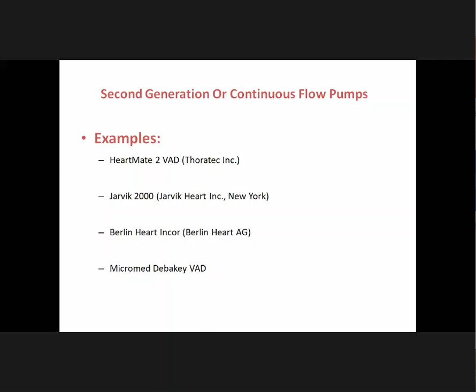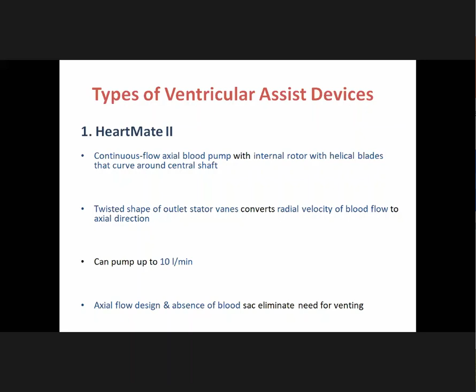HeartMate 2 is a continuous flow axial blood pump with an internal rotor with helical blades that curve around a central shaft, and it will be twisted in shape. The twisted shape of the outlet stator vanes converts the radial velocity of the blood flow to axial direction, and it can pump a volume of around 10 liters per minute. And being an axial flow device with an absence of a blood sac eliminates the need for venting.